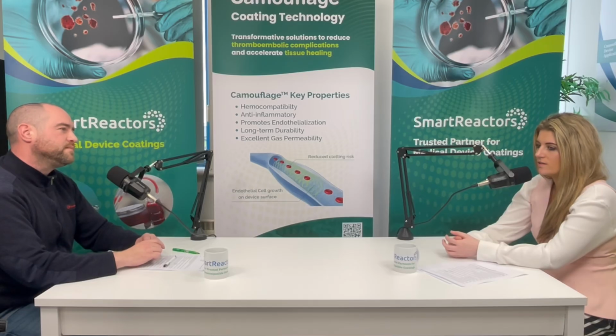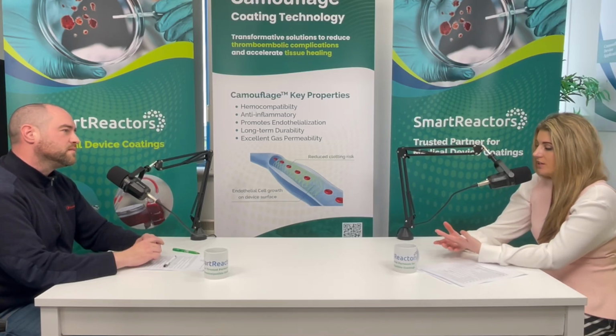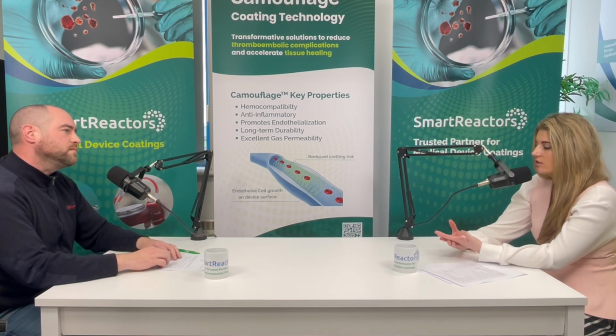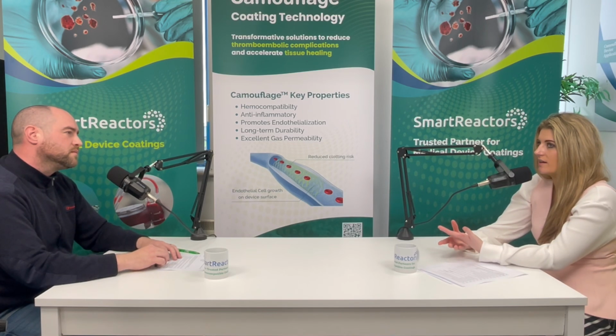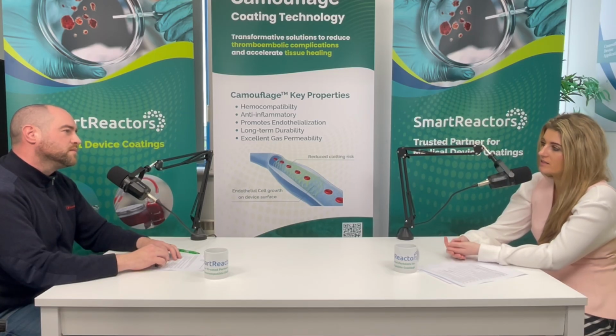Okay. And once hemocompatible coatings are applied to a particular type of device, how do medical device manufacturers, let's say, ensure that they perform with long-term stability? Yeah, it's a series of different experiments. There isn't one test fits all for everything, so you've got to ensure your coating coverage is there, that you have a method for detecting it. In the case of heparin, you have to quantify the amount of heparin that's there and the surface activity. You've got to look at your durability in simulated flow, simulated use to make sure the coating doesn't come off. And your ultimate preclinical evaluation of long-term performance is going to be in an animal model appropriate for your device.